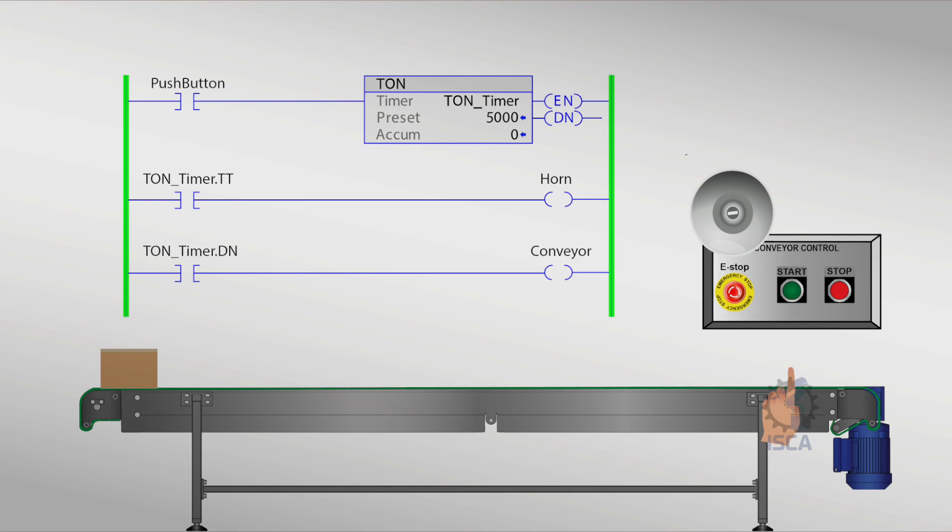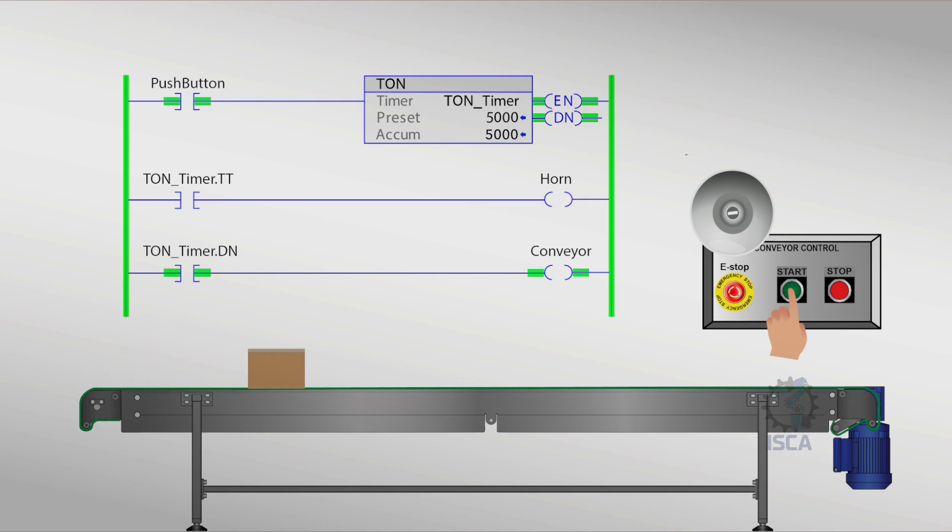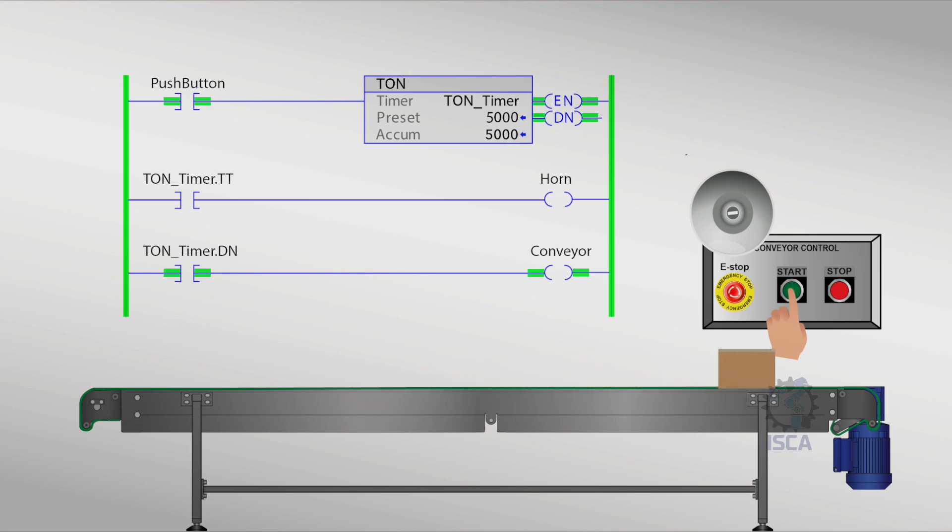For example, this can be used to delay the start of a conveyor. The timing bit, TT, can be used to signal a horn and let technicians know that the conveyor belt is starting. After the accumulated value, ACC, equals the preset value, PRE, the done bit, DN, will go high and turn on the conveyor.